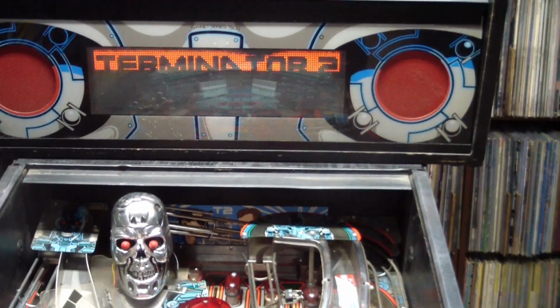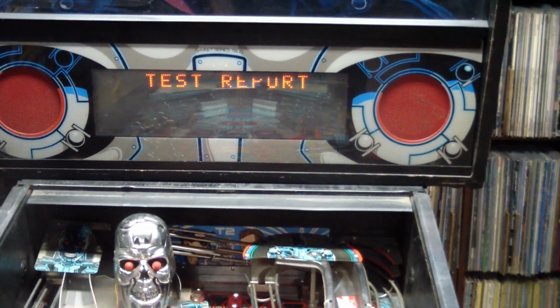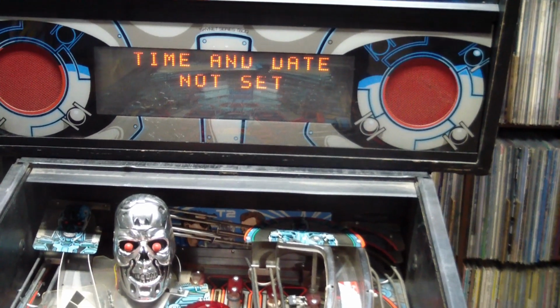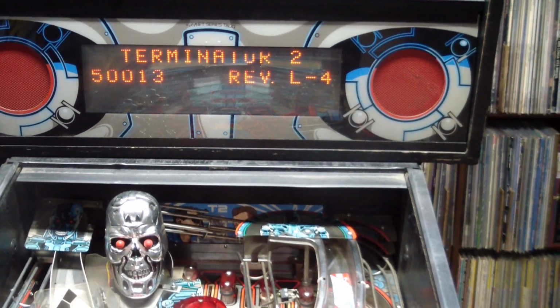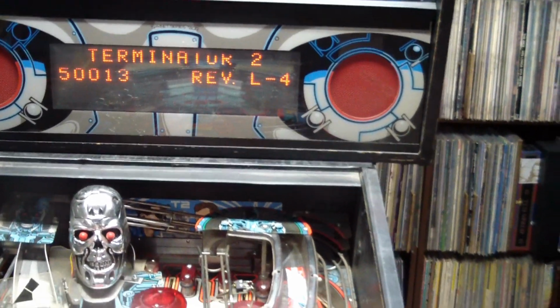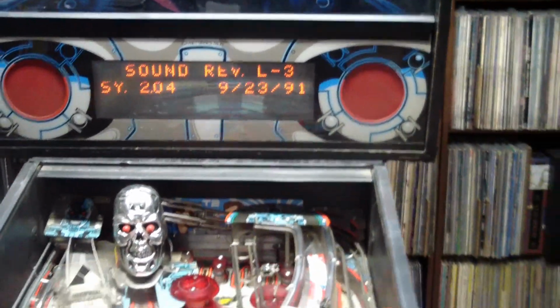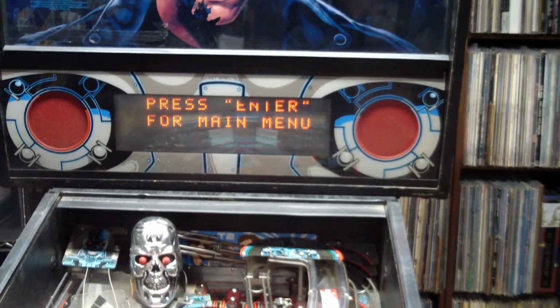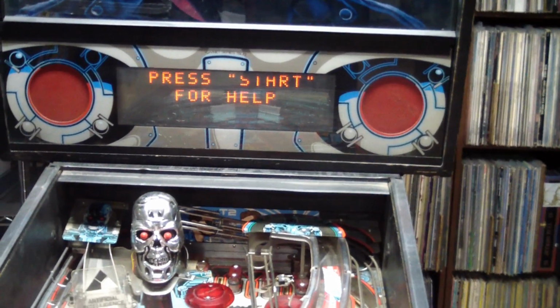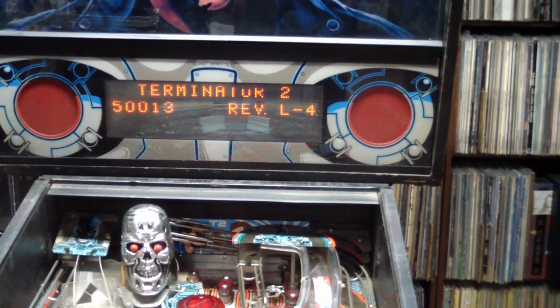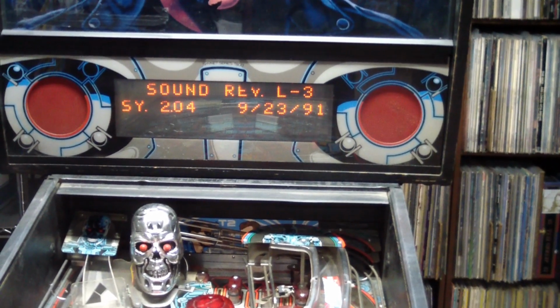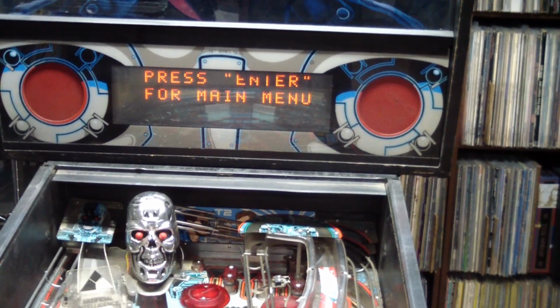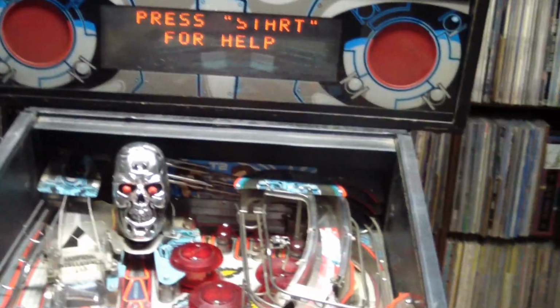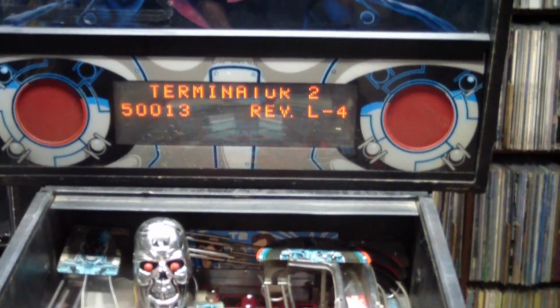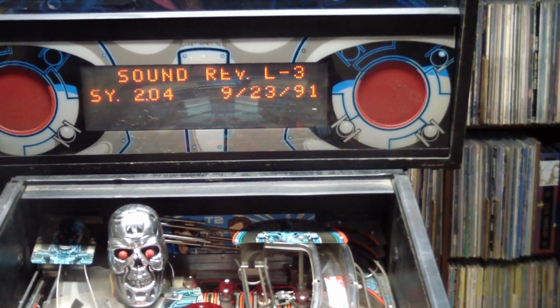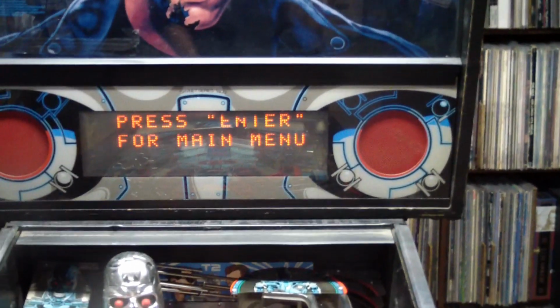supposedly tells me what's wrong, gives me the test report, but all it's really telling me is time and date are not set. And what that means is that there are backup batteries on the board that save all the settings, and those batteries are dead. So it factory resets itself every time you turn it on and plays with the defaults. And you can set the defaults, but of course the minute you turn off the machine, it forgets them all.